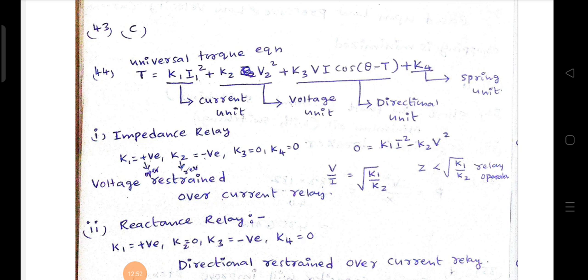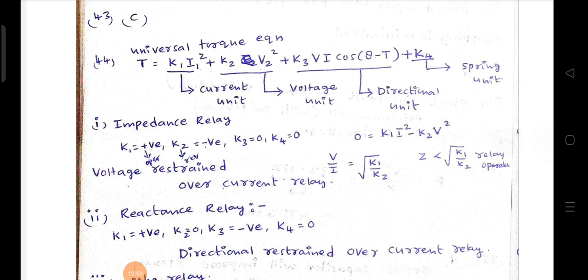For impedance relay, K2 value is negative, and this negative term indicates voltage unit. That means it's voltage restrained over current relay in case of impedance relay.